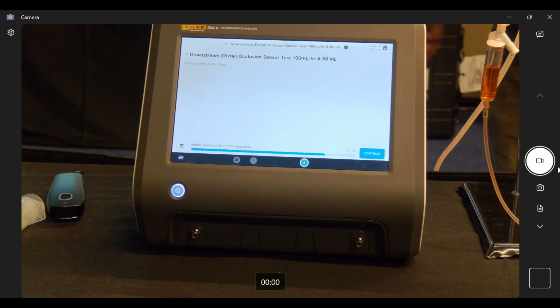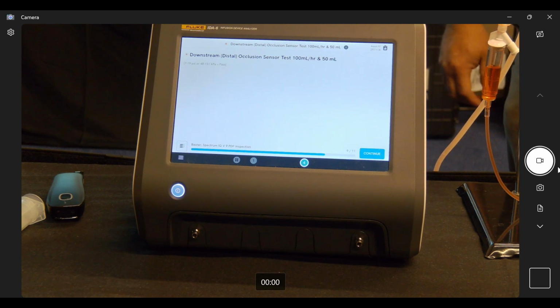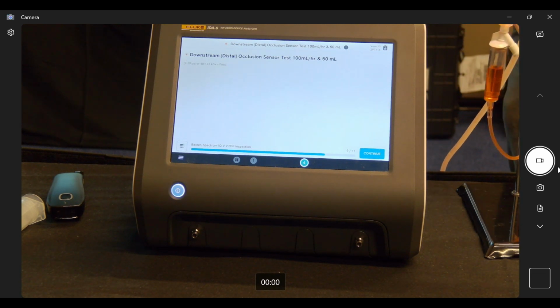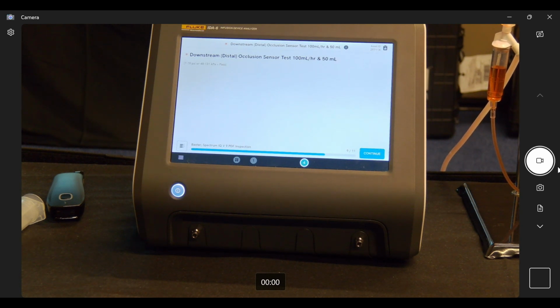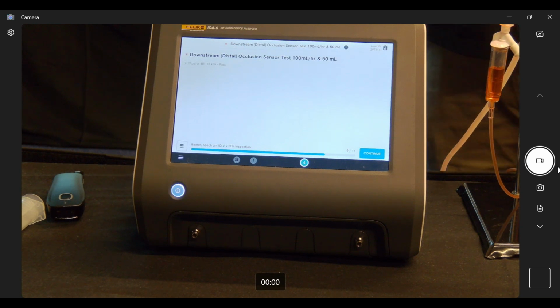So there's a few different ways I've done that. This is Baxter's actual real test set. What I did in their test is when I did that upstream occlusion test, you have to clamp off upstream, and then as soon as you clamp upstream, you disconnect, you let it run for 3 seconds, it pulls an air bubble, you reconnect, and it sucks that air bubble in. Once it sucks the air bubble in and it throws the air detection alarm, I simply open the door, and you saw how it free floated right back through the pump.